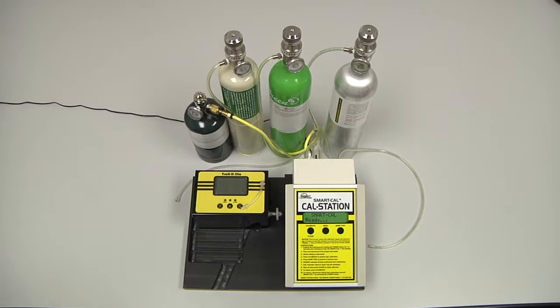To perform an automatic calibration of the TRAK-IT IIIa, we will need the instrument itself, the calibration station with instrument hose, and an adapter hose to connect the instrument hose to the TRAK-IT IIIa, as well as a fresh air hose. We will also need the calibration gas with regulators and cal adapters.